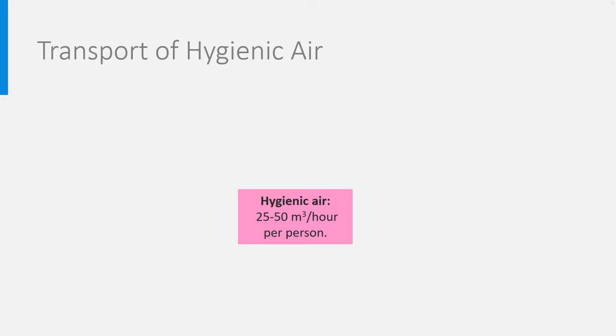Let's start with the transport of hygienic air. Hygienic air is the quantity of clean outdoor air that is needed to maintain a good indoor air quality. A minimum of 25 cubic meters per hour per person is needed, and higher values are recommended between 36 and 50 cubic meters per hour per person. It is very important that this clean air is brought directly where people need it, which is in the building's rooms. Ventilation systems can be divided into four types.